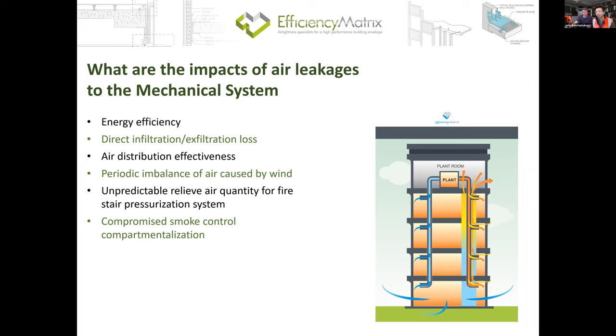I just expected that, explained that. But something maybe a bit more concerning, especially for some of you that are also in the commissioning game, is how it affects the performance of the stair pressurization system. Because if you've got a leaky building, the wind interaction would make it to some extent quite unpredictable. The relief air path where the stair pressurization system needs to tackle. So it's not just about energy efficiency and comfort. The other thing is, when we do air tightness tests, we can also at the same time test the smoke compartment, whether they are actually containing the smoke in one zone or not. So let's move on to the next slide.